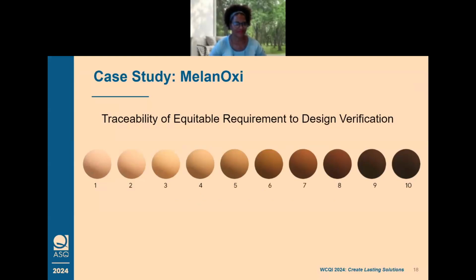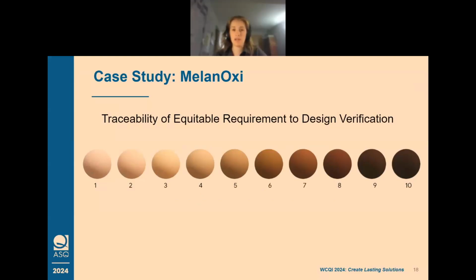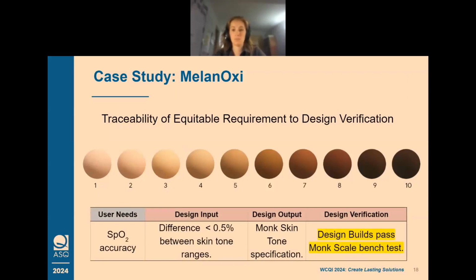So if we jump back to the case study and think about what design verification would look like in our traceability matrix, we're now at the verification stage, like I mentioned. We need to make sure the design builds pass the test for the pulse oximeter specifically. The way this is done is through an arterial blood gas test. An arterial blood gas test would actually be validation if it's done in a person, but if you replicate this, with blood pumping through a machine that's being oxygenated, and you have a human system replicated in a lab, and you do the arterial blood gas saturation test on that and compare how much light is received back by the pulse oximeter, that would be an example of how you could do it for a pulse oximeter, or ours specifically.